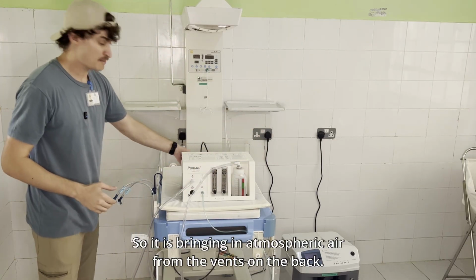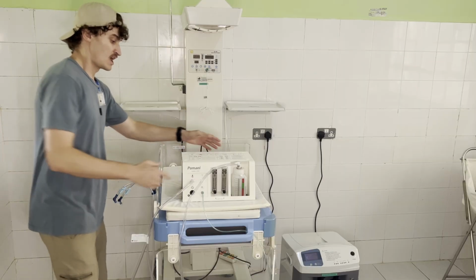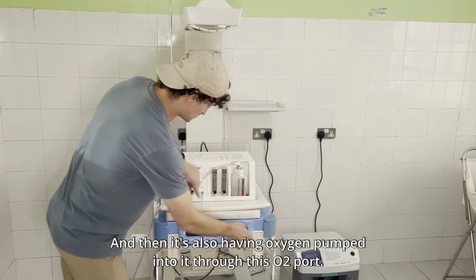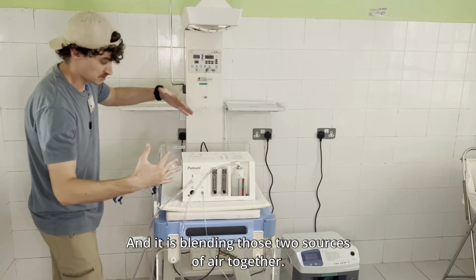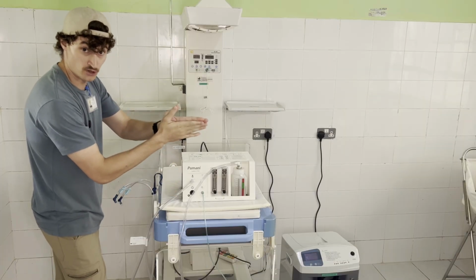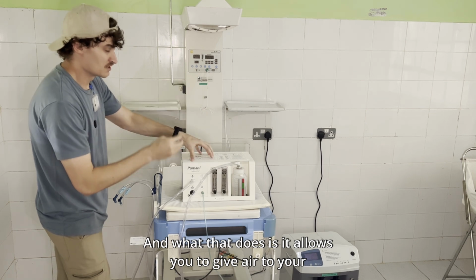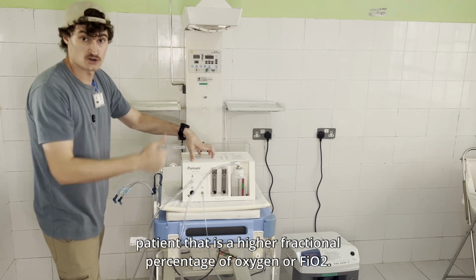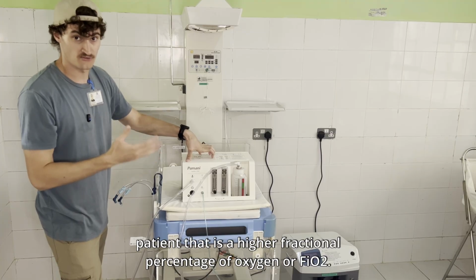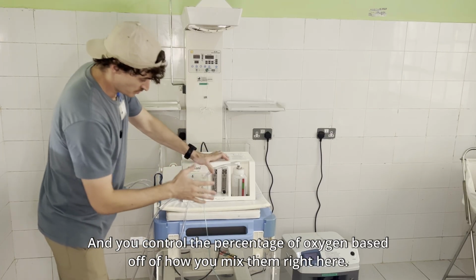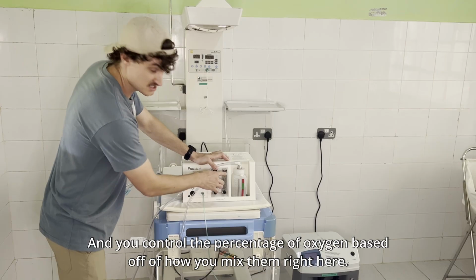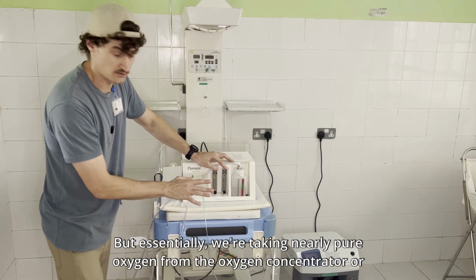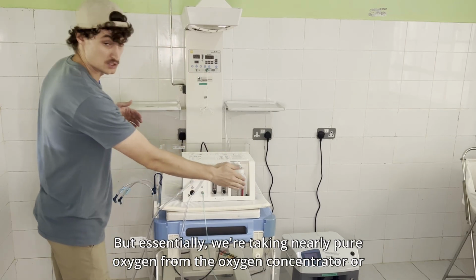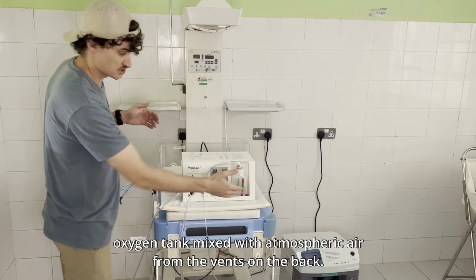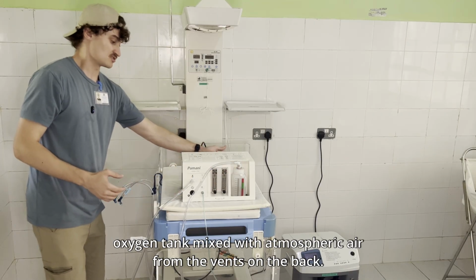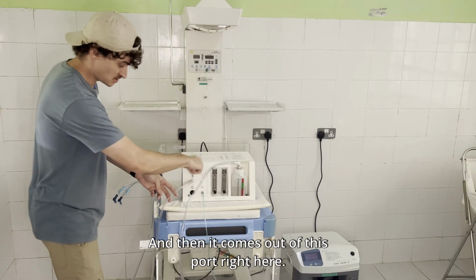So it is bringing in atmospheric air from the vents on the back. And then it is also having oxygen pumped into it through this O2 port, and it is blending those two sources of air together. And what that does is it allows you to give air to your patient that is a higher fractional percentage of oxygen, or FiO2. And you control the percentage of oxygen based off of how you mix them right here. And I'll get into that in just a second, right? But essentially we're taking nearly pure oxygen from the oxygen concentrator or oxygen tank mixed with atmospheric air from the vents on the back. It comes together and then it comes out of this port right here.